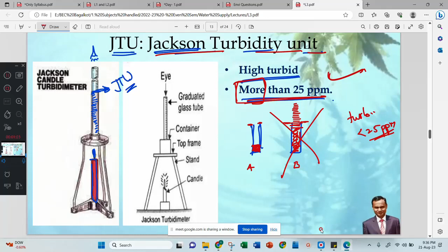If the jar height is this much, and the turbidity is less than 25 ppm, then if you go on putting that water, the light is visible even when the water is this much. Therefore, this container's limit is this much only. So it is not able to read less than 25 ppm. Therefore, Jackson turbidity is used only when turbidity is more than 25. It will not read below 25. More than 25 it can read. Right? That is the limitation.